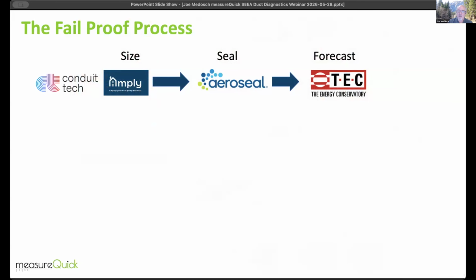This is Jim Bergmann's concept of what is a fail-proof process. So you can size the system well. You can get a quick Manual J in a matter of minutes using Conduit or Amply as an ACCA-approved Manual J process that actually walks you through the house and tells you what you should be doing. If your ducts are super bad or you need to make them tighter, which is a cautionary tale for heat pumps, you can use Aeroseal, and you're going to forecast with TrueFlow once you've got your ducts in line and know what you're going to do if you replace something.